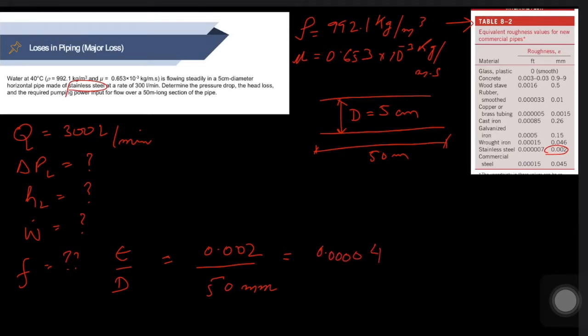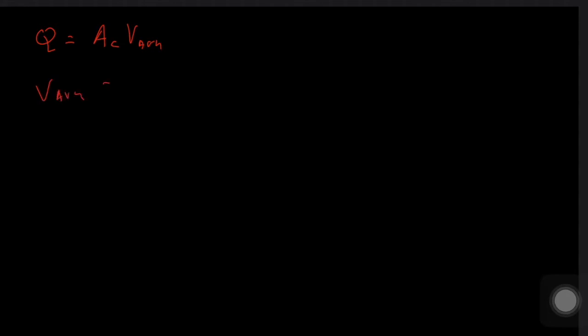Now we need to calculate the velocity. To determine whether the flow is laminar or turbulent, we calculate the Reynolds number: Re = ρVD/μ. We know density, diameter, and viscosity, but not velocity — so we use the flow rate formula to determine it. The flow rate Q equals the cross-sectional area multiplied by the average velocity.